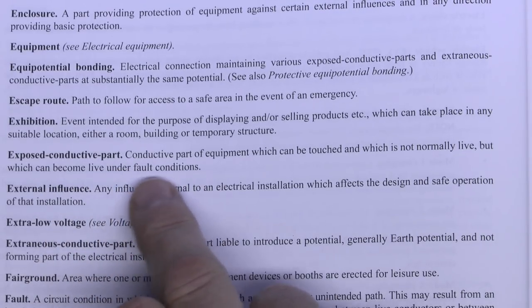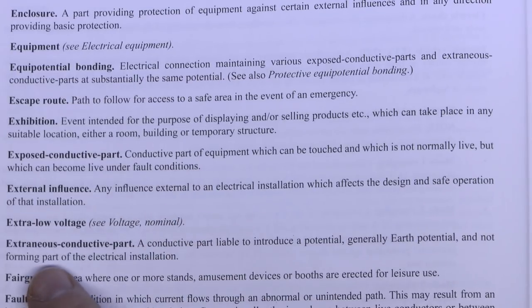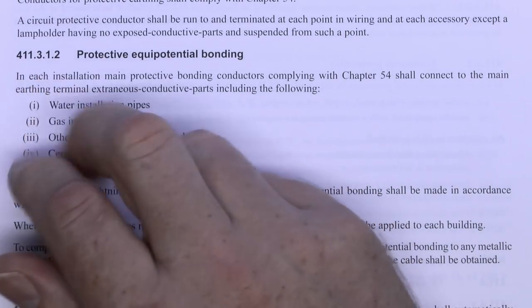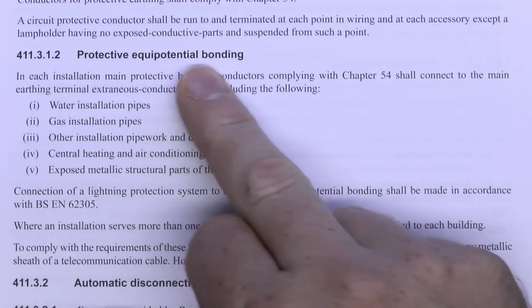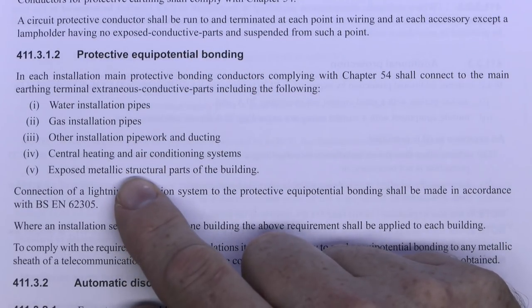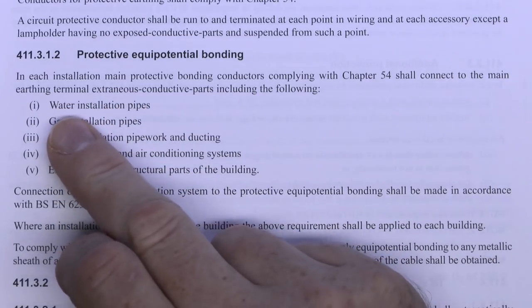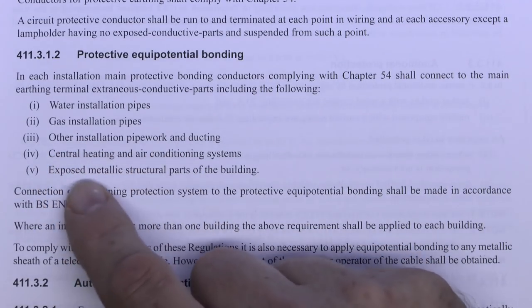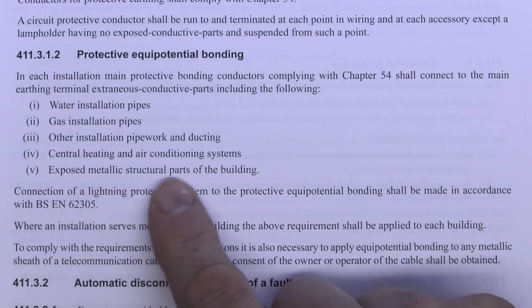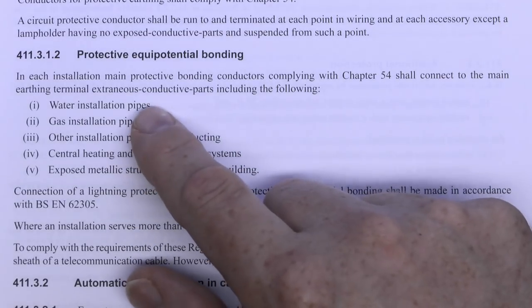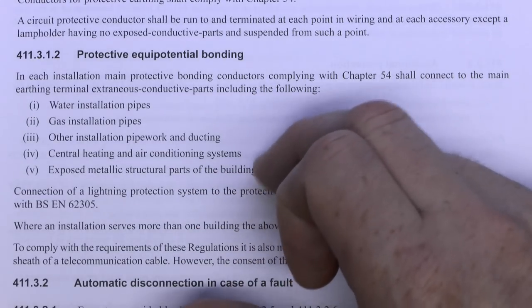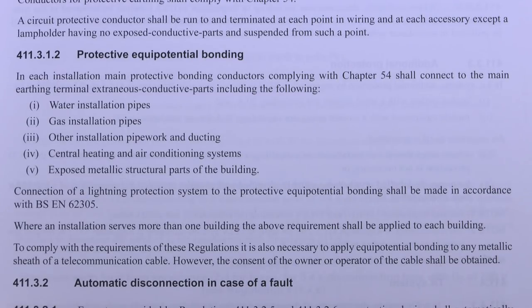It's important to note the difference between these two. The exposed conductive part is always part of the electrical installation, whereas extraneous conductive parts are not part of the electrical installation — though both are conductive. Regulation 411312 on protective equipotential bonding gives examples of the most common items considered extraneous conductive parts: water installation pipes, gas installation pipes, other installation pipework, central heating and air conditioning systems, and exposed metallic structural parts of the building. Water and gas are by far the most common.